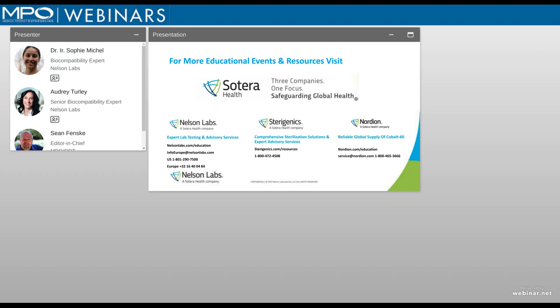included in that. So we haven't specifically addressed that in the standard, but if you run the standard assay and you fail, and you can identify it's most likely due to this addition, then you start running some risk analysis. Does this actually pose a risk to the patient? I mean, we're seeing an irritation in a very sensitive system. Is it used clinically already? You go down this risk assessment path and determine maybe we do some adjustments in the method to account for a clinical exposure as well. So that's a long answer to say it's not included in the standard, but the thought process to address that is included in -1 and also in -23, looking at a risk-based approach.